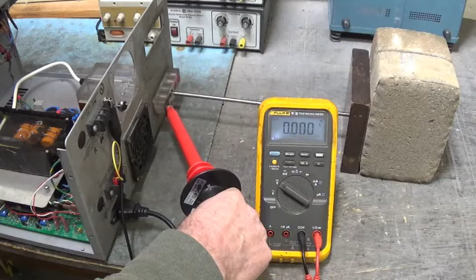Okay, I'm increasing the potentiometer, and the meter says we're at 10 kilovolts, and we have 10.03 volts on the meter, indicating that we have 10,000 volts at that probe tip right there. Let's increase it. I have 15,000 volts on the meter of the charge master, and I've got 15.62 on the Fluke meter there. There's 20,000 volts on the meter of the Charge Master and 20.71 volts on the Fluke voltmeter.